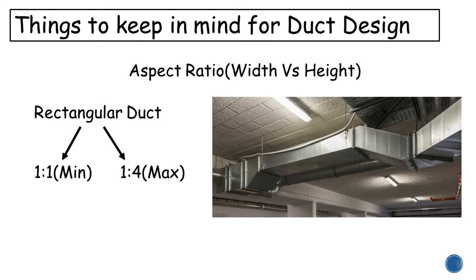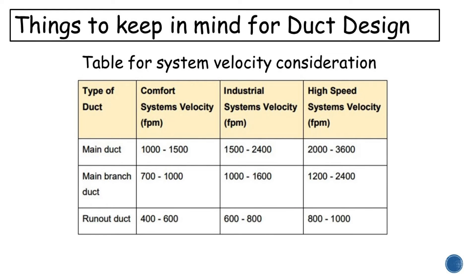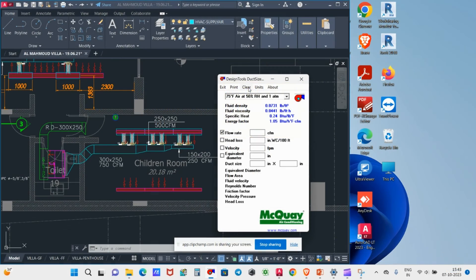The upcoming demonstration shows how to design duct using McQuay Duct Sizer. I considered an airflow rate of 750 CFM and the calculation method is the equal friction method. After opening the duct sizer, you have to set the air properties and units. Since the application is residential, I considered 1000 FPM as the velocity.